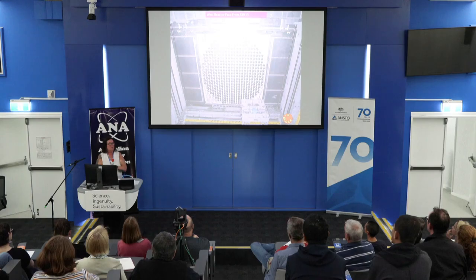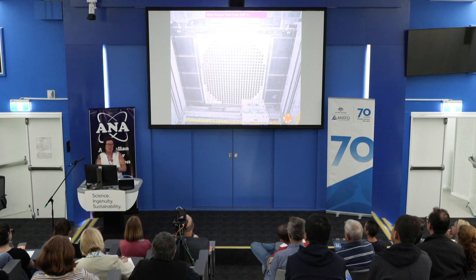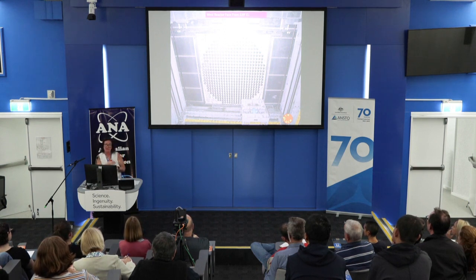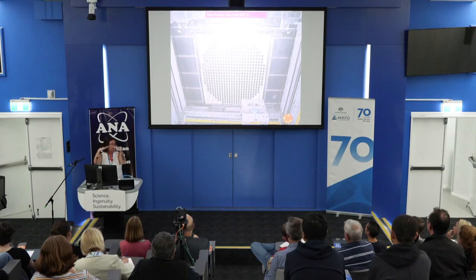We also use the fueling machine to move people. During an outage, we have to go up and down the face to check that our fuel channels are still healthy, doing a scrape and checking that the springs haven't moved. Sometimes we do something called a lithium lick, where we clean the lithium off the end fittings. So we use the fueling machine with a giant platform to move people up and down the face to do their inspections and repairs.